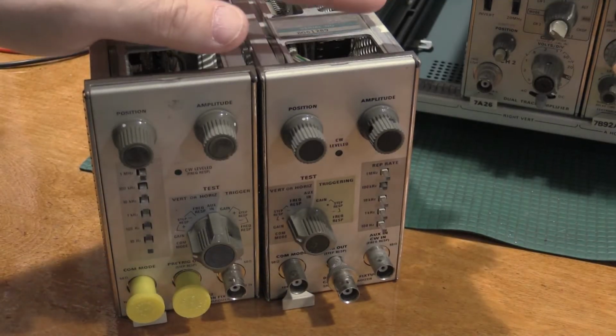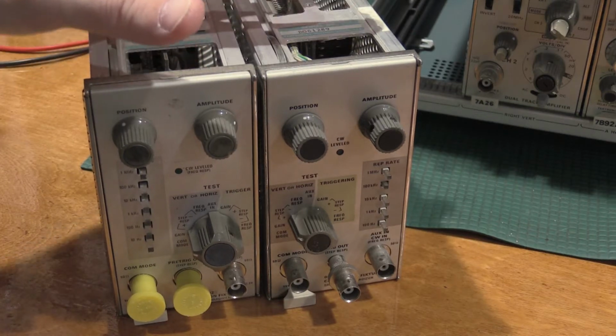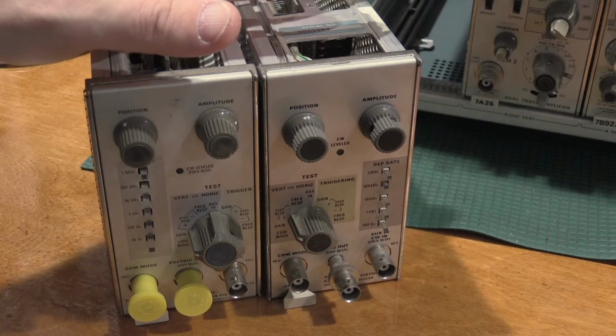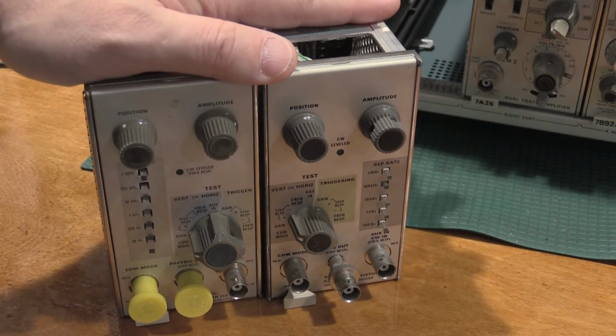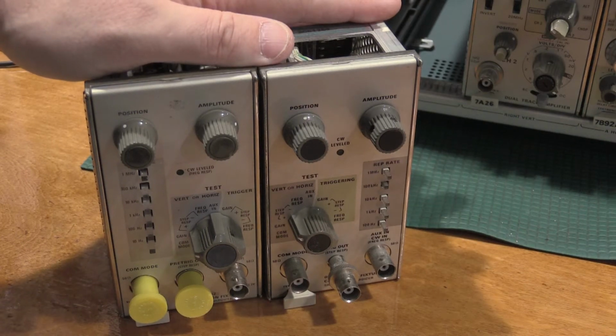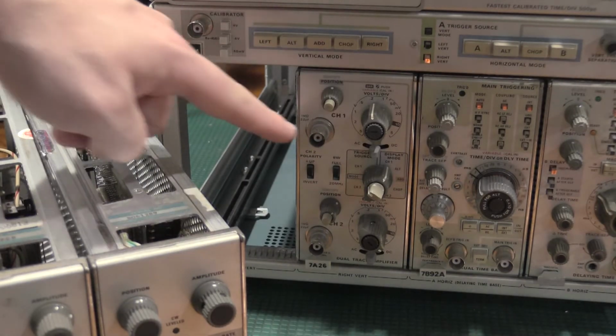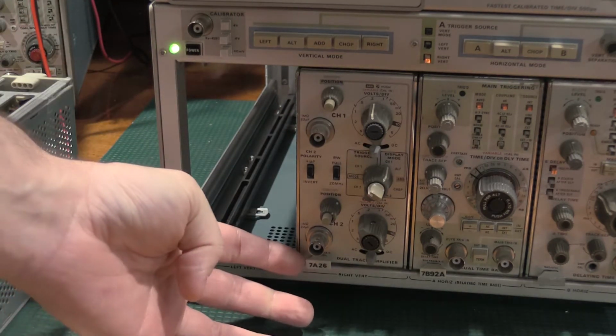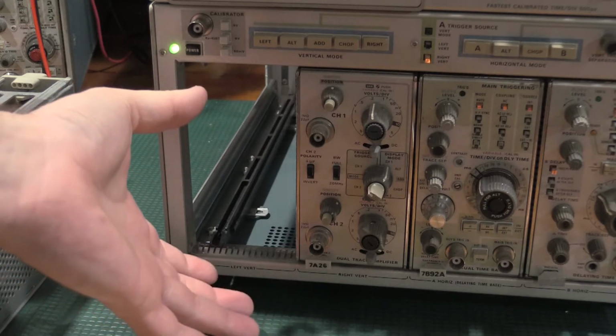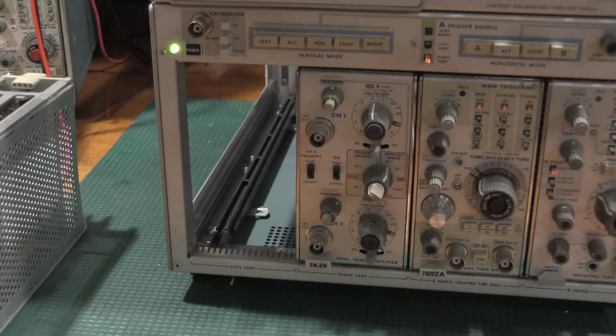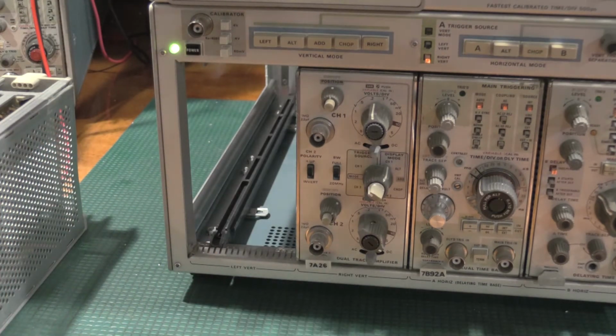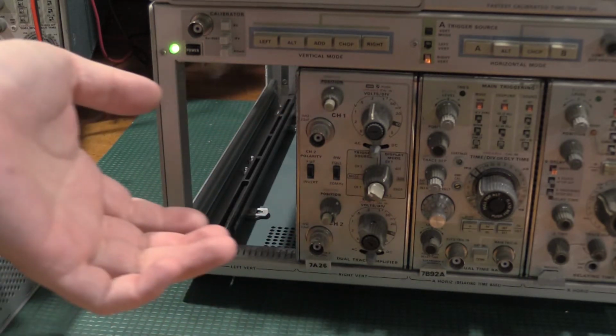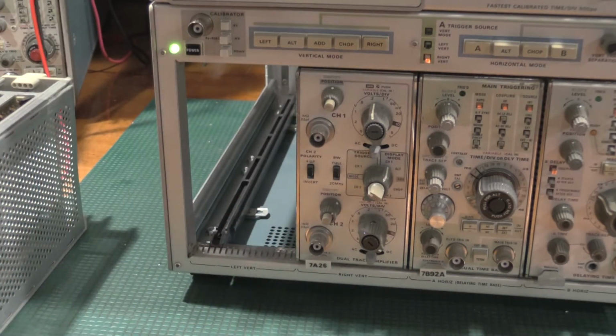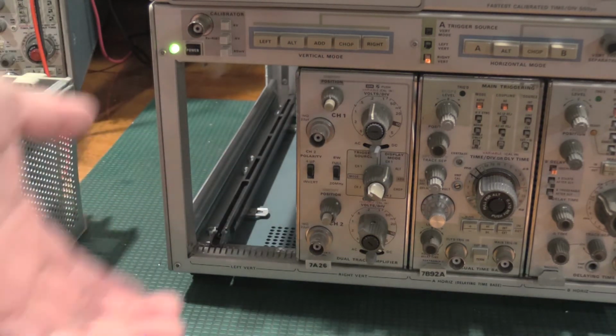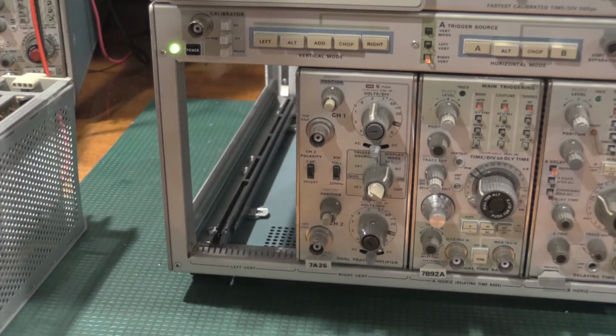I get a lot of questions, and I see a lot of questions about these calibration fixtures and signal standardizers. The answer to the question of, do you need one of these to calibrate the scope? No. A scope cal can be done with a vertical amplifier and a time base. So what you lose is the normalization between the two bays. So if you calibrate it with a vertical plug-in, you're not guaranteed that the scope will still be in spec if you pull this out and move it into the other bay. So you can calibrate it that way. However, the calibration can be thrown off given the response of the individual bays. So that's what the standardization fixtures do. They allow matching between the bays so you can move plugins in and out and things like that, and the scope still be in spec.